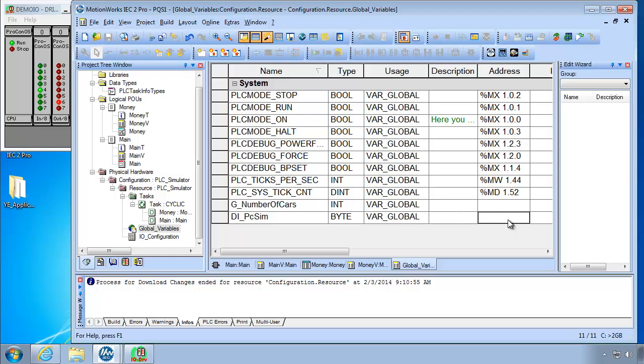So we'll type in BY byte. Let's skip ahead to the address. And the address is %I for inputs. And now don't type an X like you may have done before. Use B for byte. We're doing the whole byte. And 0. It's byte 0. No dot at the end if it's a byte. Only for bits with the X indicator.